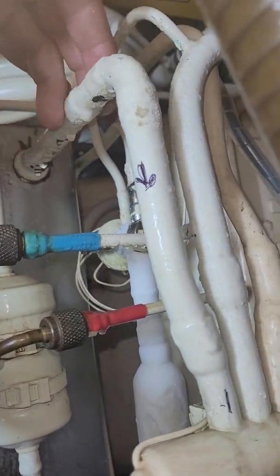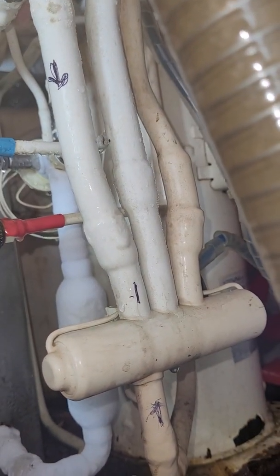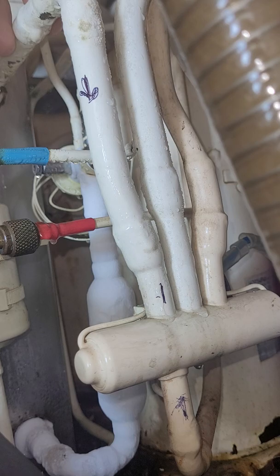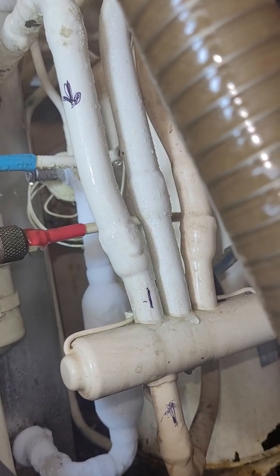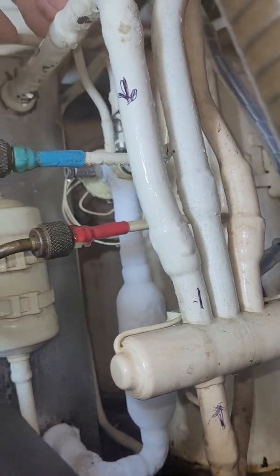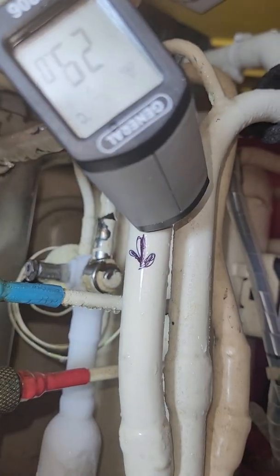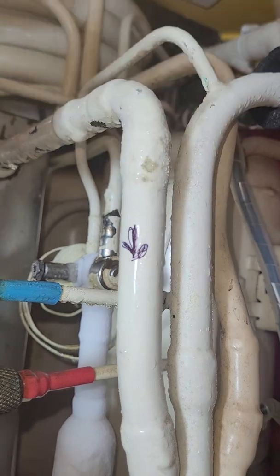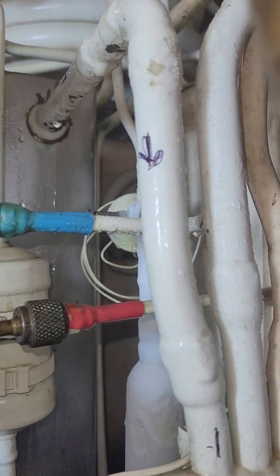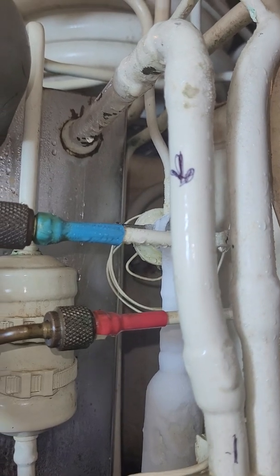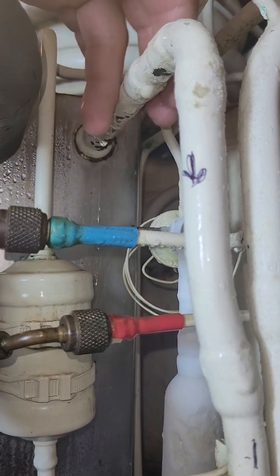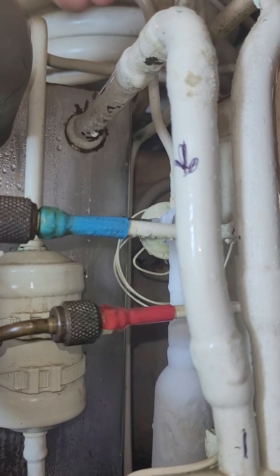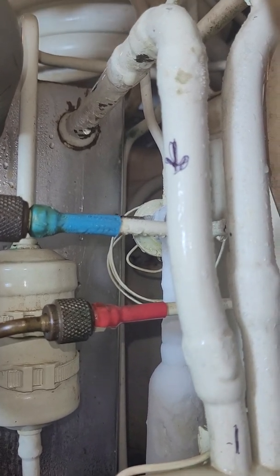So it comes back out, it's expanded. And what we're looking for is how much higher this temperature is versus its saturation temperature. The refrigerant saturation temperature at a certain pressure, how much higher is the temperature in this pipe. So to see that, we can see our pressures here. We're running here at about 40 psi on the suction side. So then we know our saturation temperature, and then we can take the temperature reading on this pipe and see how much higher that is. And that's called the superheat. So the superheat is the difference between the saturation temperature of the gas and the actual temperature coming out. So how much more thermal energy has the gas absorbed after its state change.